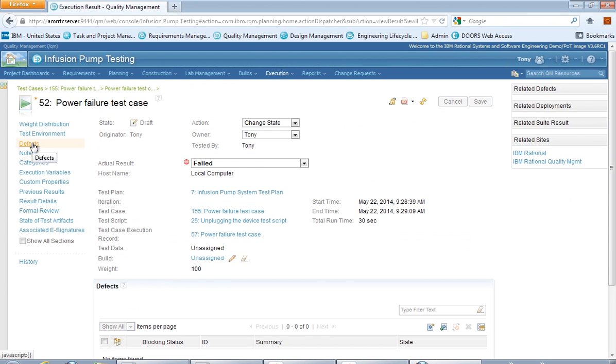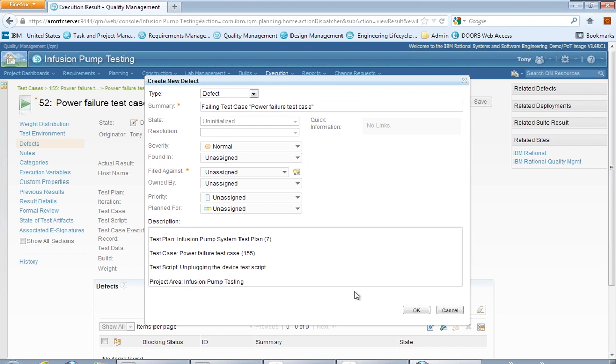We start the infusion pump application, set the channel to 1, press the load button. Press the load button again, check the right amount, unplug the unit, start the unit again. What we're going to do is say fails, and then I'll fail all the remaining steps.